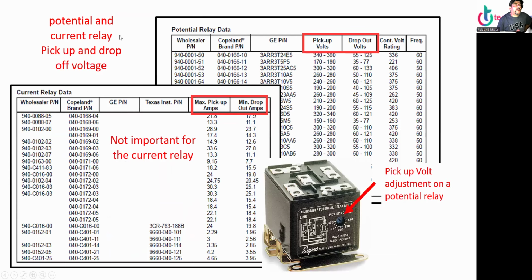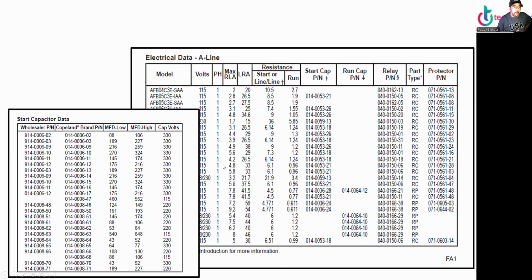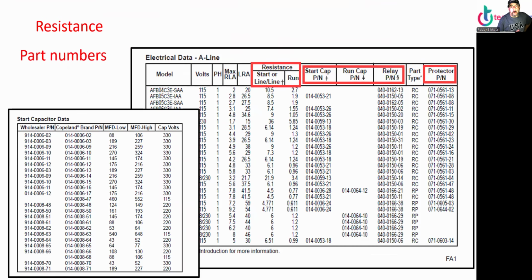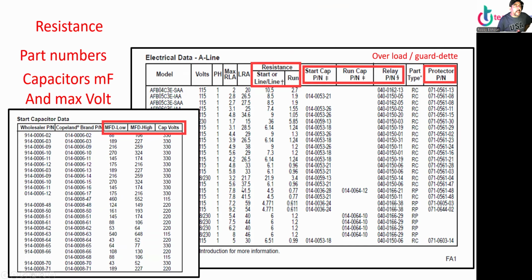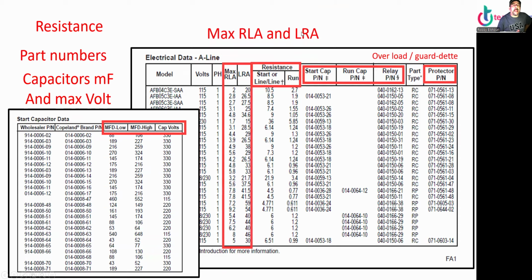Now, there's a lot of useful information in the Copeland book or the Tecumseh book, whichever manufacturer. Potential relay pickup and drop-off voltage. I'll explain this one later. And we have the resistance. We have the part number. The overload, or sometimes they call it a guard. And the microfarads, maximum RLA, and locked rotor amp.